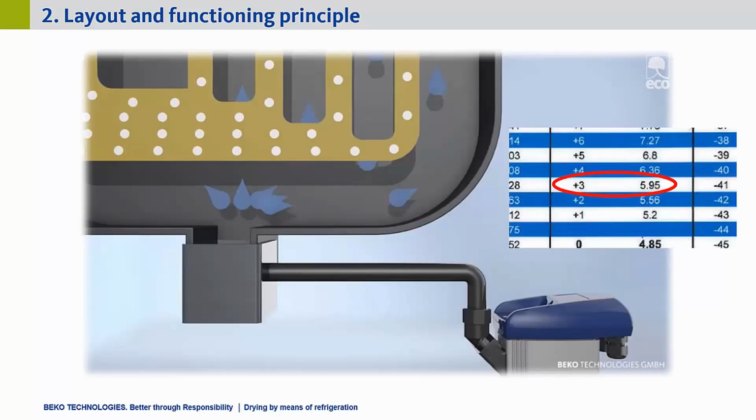So often when we ask the question, where does the air get dry? We hear the answer that it is at this point because all the excess water vapor has now condensed out. But is this really true? Does the air get dry? To answer this, one must remember when air is considered dry. The whole thing is an interaction of temperature and humidity, and thus the dew point. It is not important which dew point we have, but how high the relative humidity is.